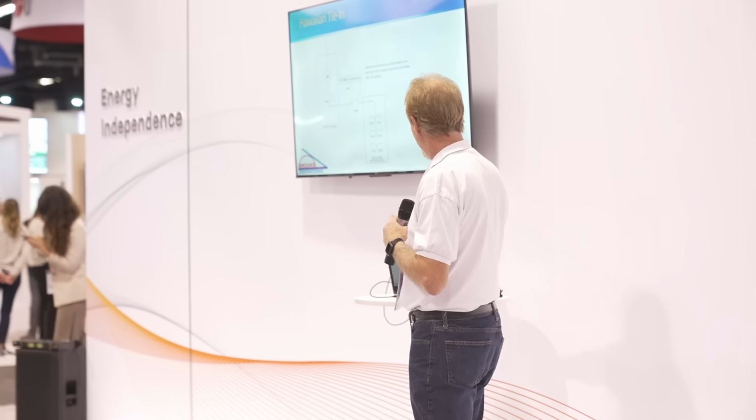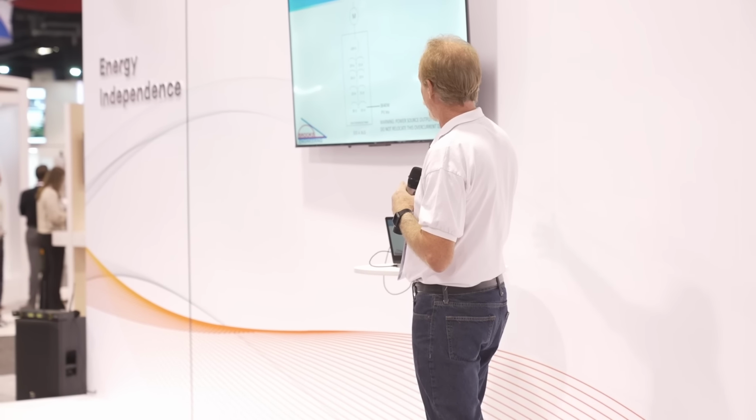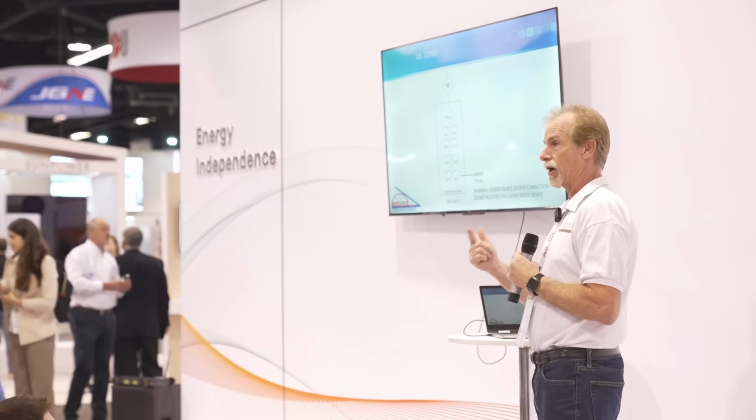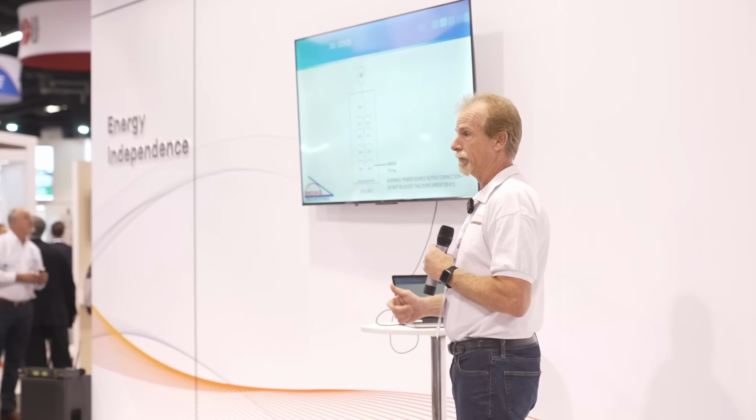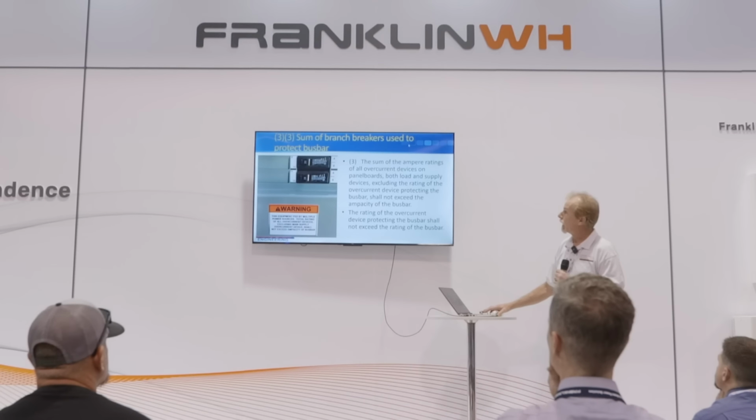Well, what if you don't have a meter main? Well, there's the old school 120% rule. You can put a 3.8 kilowatt PV system on that 100 amp service, ladies and gentlemen. Thank you very much. Now consider all your transaction costs: how much money are you going to make on that job? Probably not a lot. Everybody knows that.